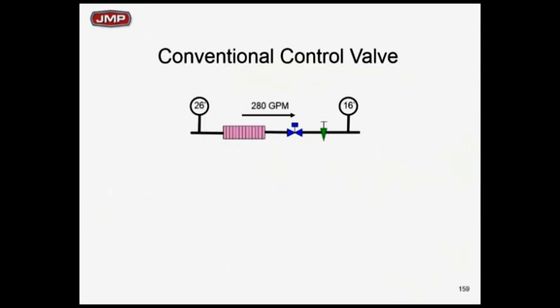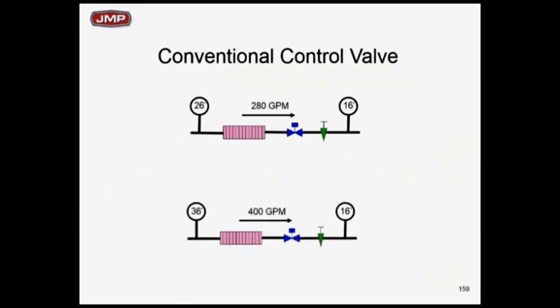Here's a two-way valve. Let's say this system is a 500 GPM coil. I got a good two-way valve in here. Inlet pressure is 26 feet. Outlet pressure is 16 feet. I got a valve set for 280 GPM, a conventional everyday two-way valve. What happens to the flow rate through this coil and through this two-way valve if I increase the differential pressure? I'm not going to change the position of the valve. I'm going to hold the valve position right where it is. I'm just going to increase that 26 feet to 36 feet. Still got 16 coming out. I got 10 feet of head across at 280 GPM.